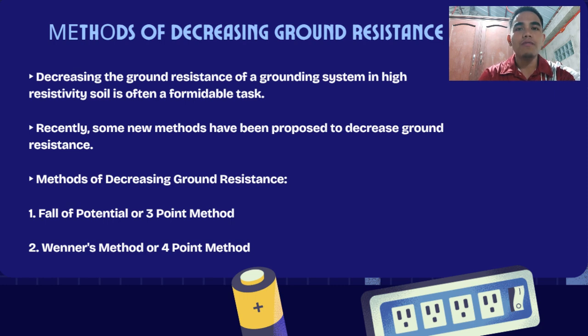So first is the fall-of-potential or three-point method. It's a simple way to measure how good an electrical grounding or earthing system is. You use three rod points in the ground. For example, the ground rod is the one you are testing, the current rod is placed far away, then a potential rod is placed in between. How does it work? A test instrument sends a small current from the ground rod to the current rod. Then it measures the voltage between the ground rod and the potential rod. Using voltage and current, it calculates resistance with Ohm's law.